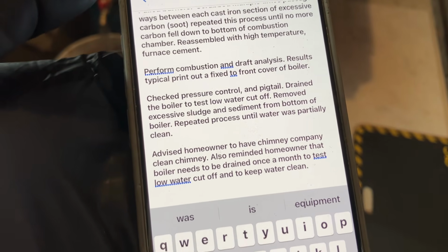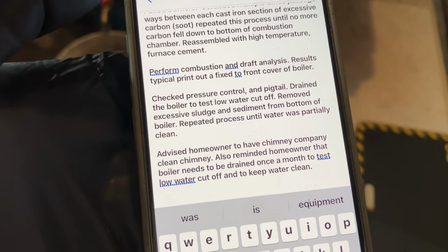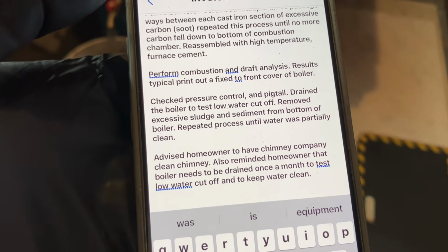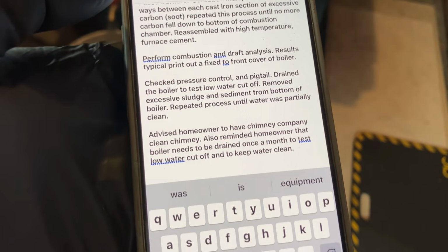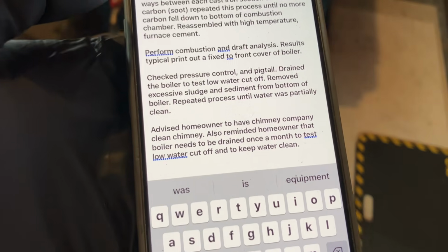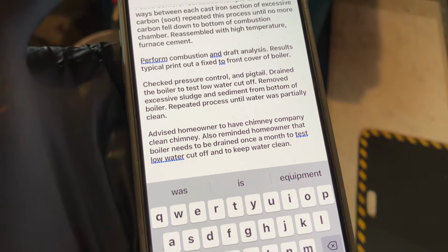drained the boiler to test low water cutoff, removed excessive sludge and sediment from the bottom of the boiler, repeated the process until the water is partially clean, which it almost is. Advised homeowner to have a chimney company clean the chimney.